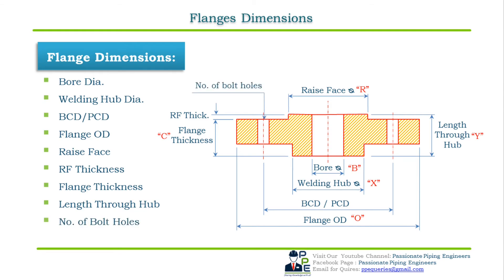Number of bolt holes is the number of bolt holes a flange has for mating with other components. Bolt holes are in multiples of four and shall be equally spaced; pairs of bolt holes shall straddle fitting centerlines. Bolt hole diameter is the diameter of the bolt holes on a flange through which the bolts are passed and bolted to the mating flange.